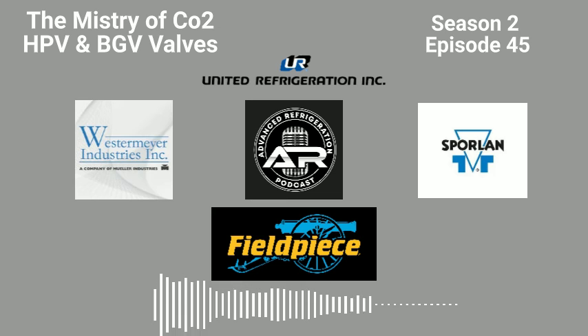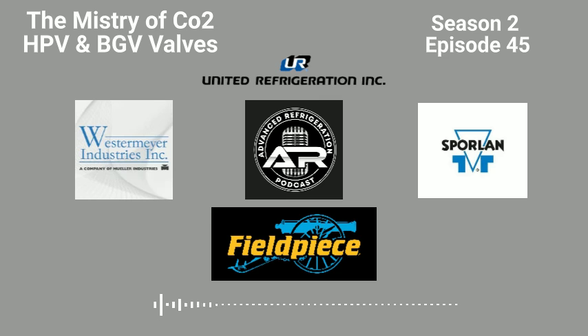The first one we came out, it was 4 to 20 milliamps, and it was throwing everybody for a loop because it wasn't set to 0 to 10 volts. And by the time it got caught, it was a problem. So it needs to be set up for 0 to 10 volts if that's what you're using instead of 4 to 20 milliamps. So that's one thing. They seem to get a little bit better. The description file is still a little rougher on the edges. You can't use the overrides on the screen, which is super frustrating.